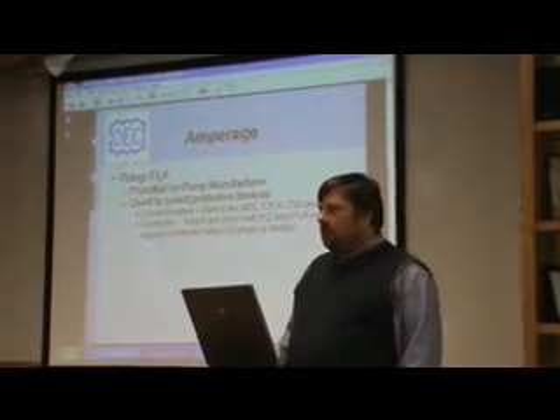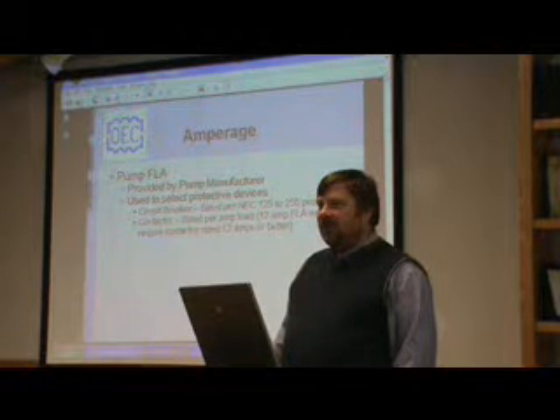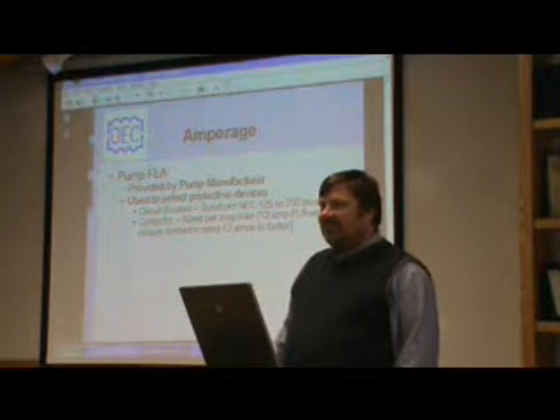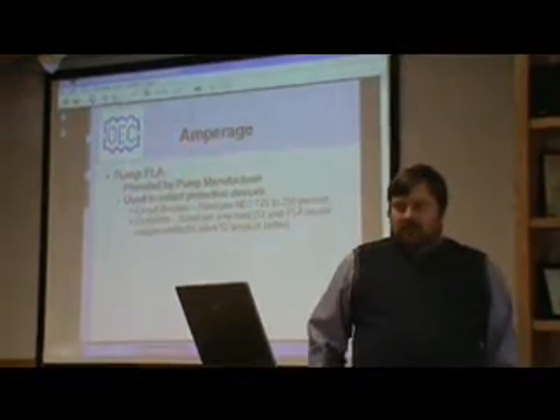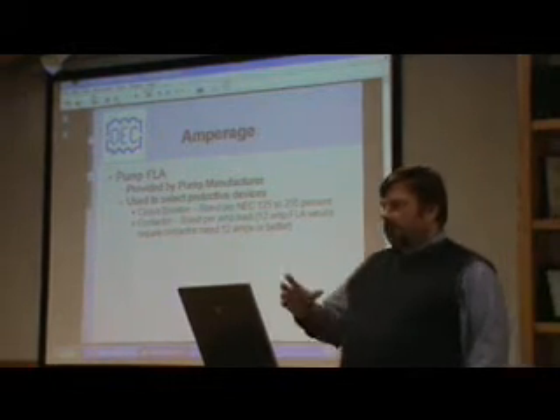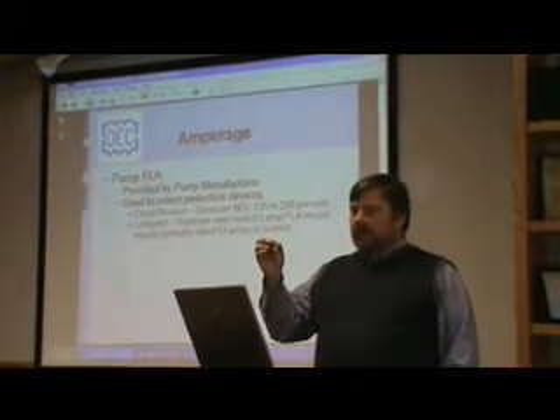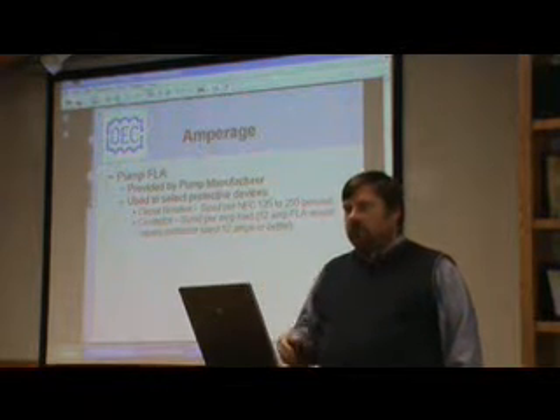Does anybody know what the contactor does inside a panel? I know Ross knows. What's the contactor do, Ross? Yeah. The contactor is basically just a big relay that you use the 120 volt control through your hand switch or through a float switch to pull the contactor in, because it has big contacts to hold the amperage that the motor's rated for. So it's just nothing more than a big high power rated relay.